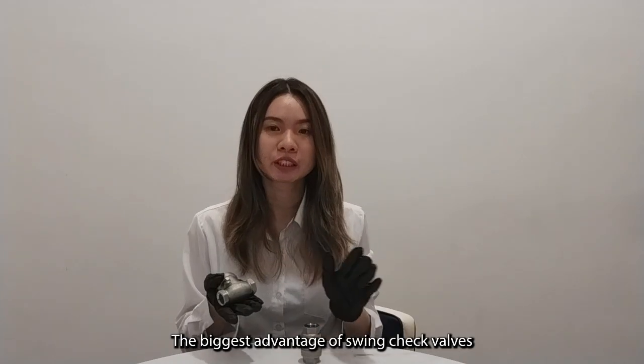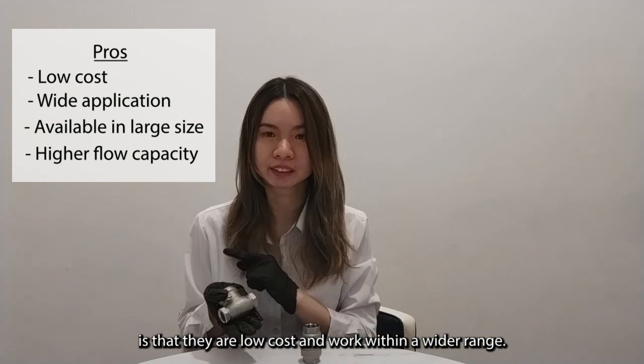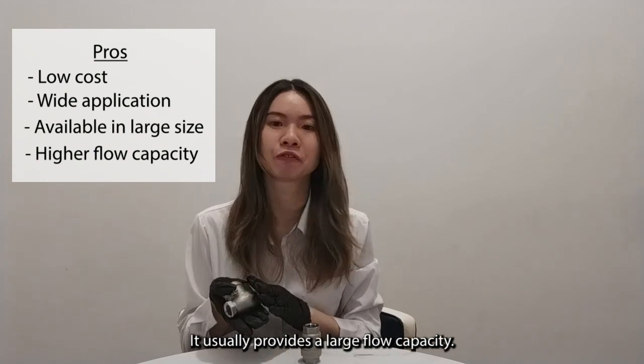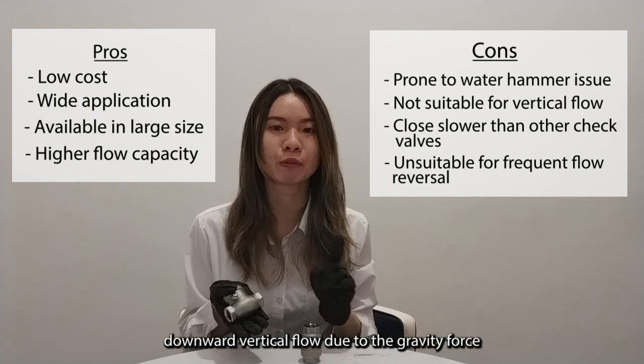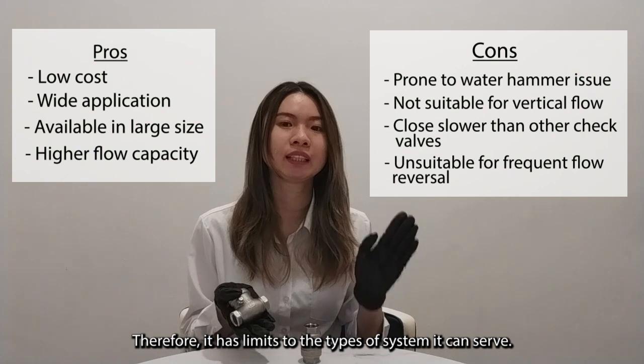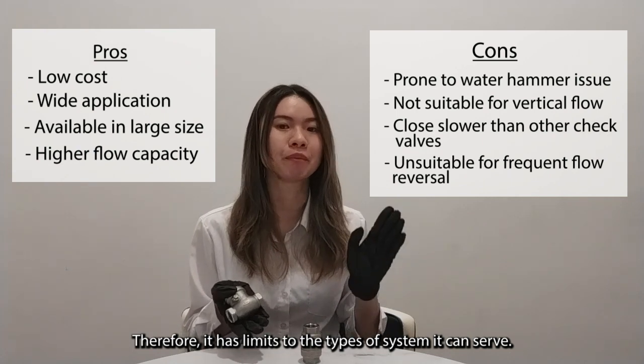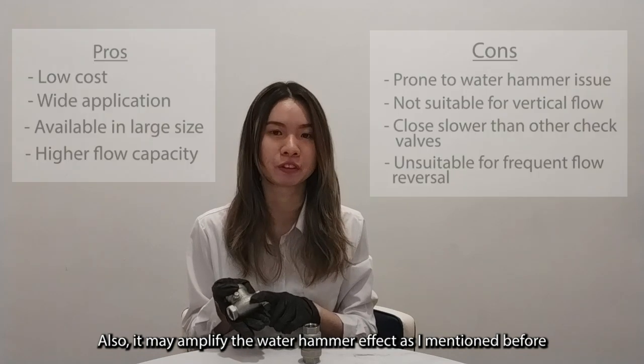The biggest advantage of swing check valves is that they are low cost and work within a wider range, and they usually provide a larger flow capacity. However, this valve does not support downward vertical flow due to the recovery force required, which limits the pipes or systems it can serve. Also, it may amplify the water hammer effect as mentioned.